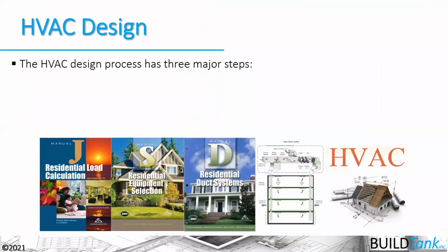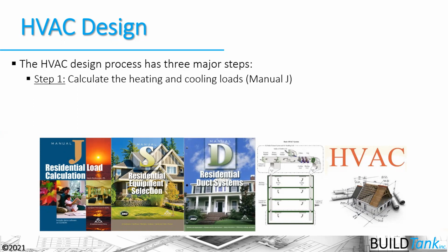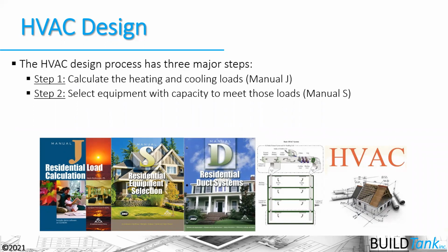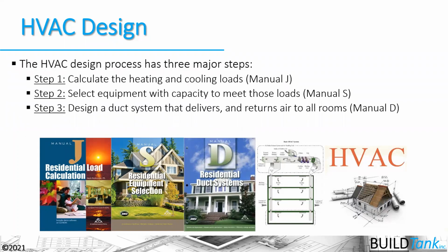Now, this HVAC design process has three major steps, and they're not that difficult to do because we have lots of good software out there, and they're defined by ACCA through Manual J, S, and D. The first step is to calculate the heating and cooling loads. That is what the Manual J process is all about. The second step is to select the equipment with the capacity to meet those loads, and that's what Manual S is about. And the third step is to actually design how those loads are going to be delivered around the house. That's the Manual D part. How do you design the duct system to deliver those loads?